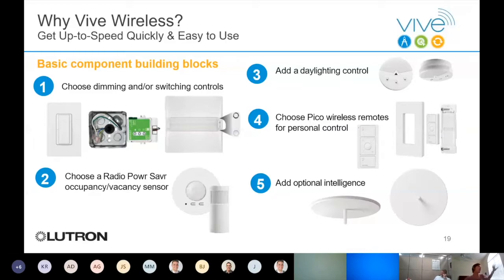This sensor is the sensing portion. So if I've got a window that's like 6 feet tall, you'd put this on the ceiling facing about the center of the window or facade, about 1 to 2 times the height depth inside of the space. So if it's 6 feet, I'd put it 6 to 12 feet away from that window on the ceiling. Really easy to use, just slap it on there.